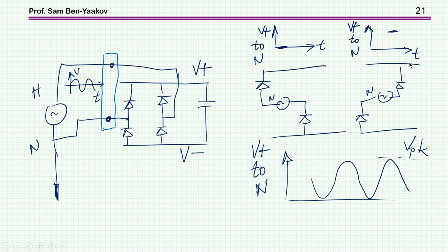So if we look at this bus, we see low, neutral, almost ground, and then high. It looks something like this. This is the voltage here referred to neutral, not between these two points, or between these two. Between these two there is a DC, between these two there is an AC. We are talking about the voltage here referred to the neutral, so we have a low frequency component on the bus referred to the neutral.